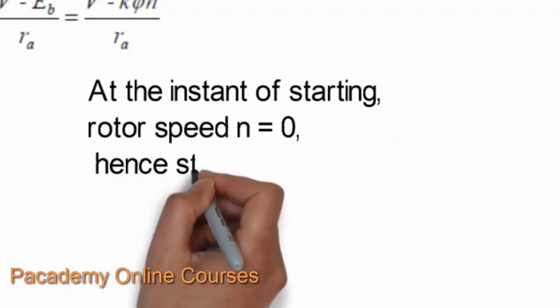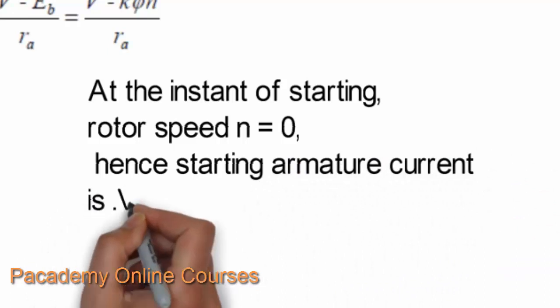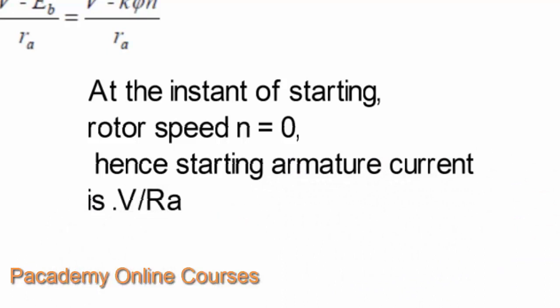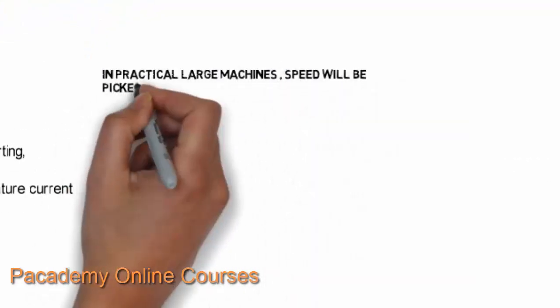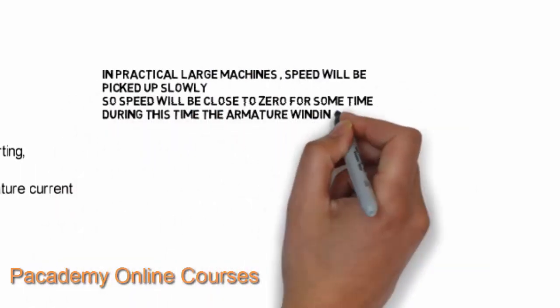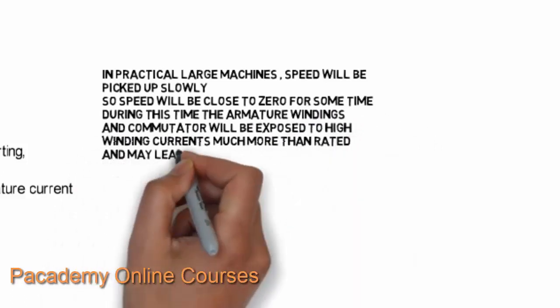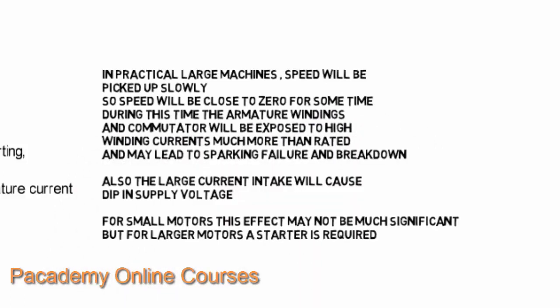At the instant of starting, the rotor speed is zero, so the back EMF is zero and the current will be very high — directly equal to V divided by R_A. Such a large current could damage the armature windings and cause sparking in the commutator segments. In large practical machines, speed is picked up slowly, so the armature windings and commutator are exposed to high currents — much more than rated — for some time, which may lead to sparking, failure, and breakdown.